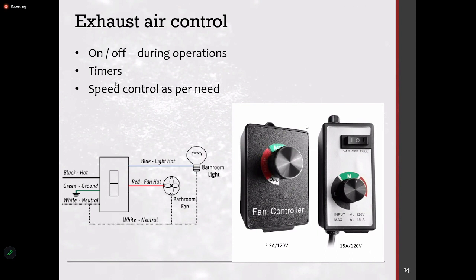So during the day when the office is in operation, you can ensure the exhaust fans are running continuously, or you can run it for about 15 minutes every 1 hour, or you run at about 5 minutes, then the next 5 minutes it is off. So some amount of time interval you can set for the fan to operate, because not only when the odor is generated, so when you switch on the bathroom lights and come in, the odor will be there. So generally the fan should operate actually after somebody uses it. That is where the requirement is. So that's why generally we don't recommend, for medium traffic or high traffic, coupling the exhaust fan to the bathroom light.